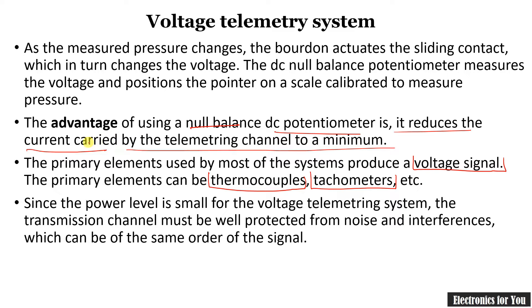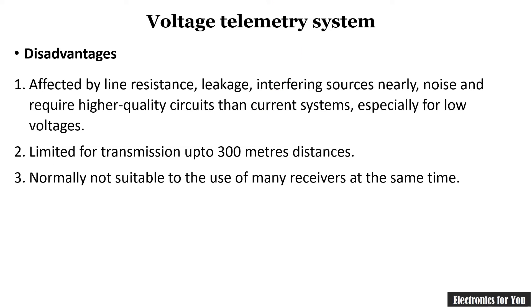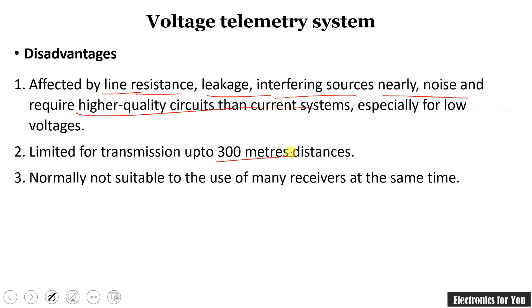The power level of a voltage telemetry system is low and therefore it can be affected by noise. The disadvantages of the voltage telemetry system include: it is affected by line resistance, leakage, interfering sources, and noise, and therefore a higher quality circuit is required. Its range is limited to 300 meters and it is not suitable for use with many receivers at the same time.